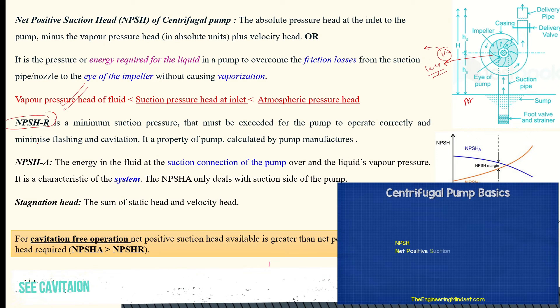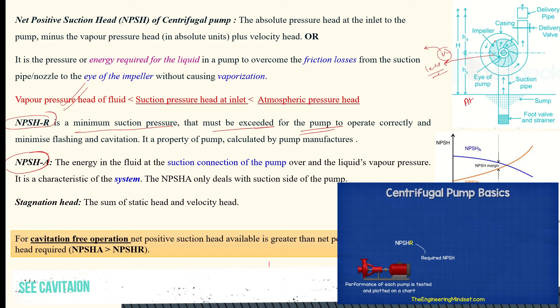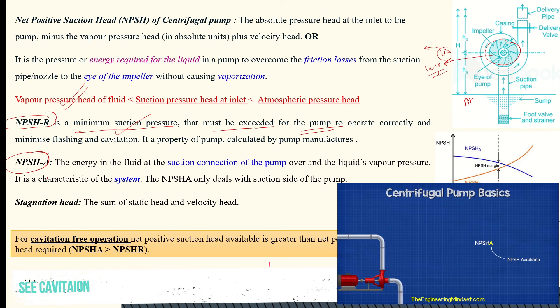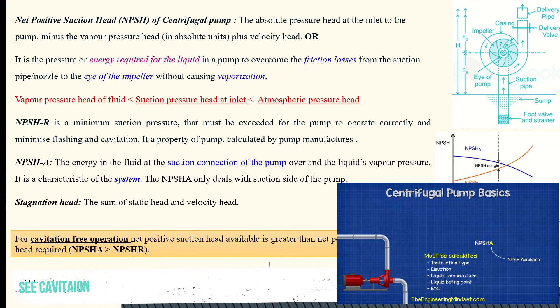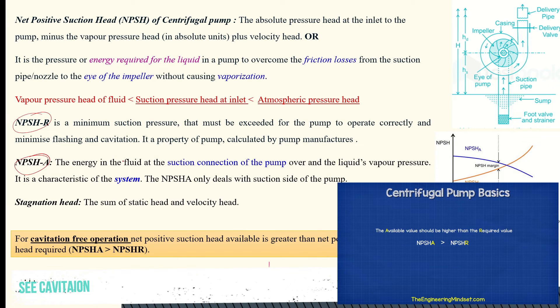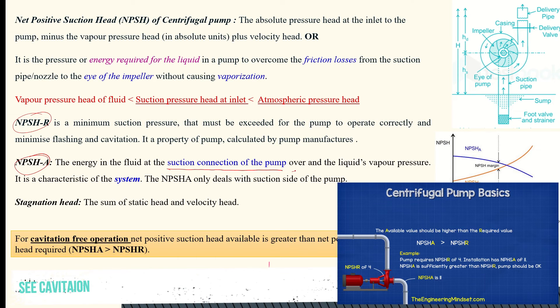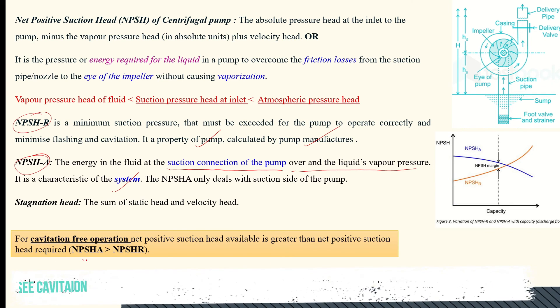NPSH has two types: NPSH required and NPSH available. NPSH required is the minimum suction pressure that must be exceeded for the pump to operate correctly — the minimum head needed so water can move from the source to the impeller. NPSH available is the actual head available in the system — the energy in the fluid at the suction connection above the liquid vapor pressure. NPSH required is a characteristic of the pump, determined by the manufacturer. To avoid cavitation, the pump should be operated when NPSH available is always greater than NPSH required.